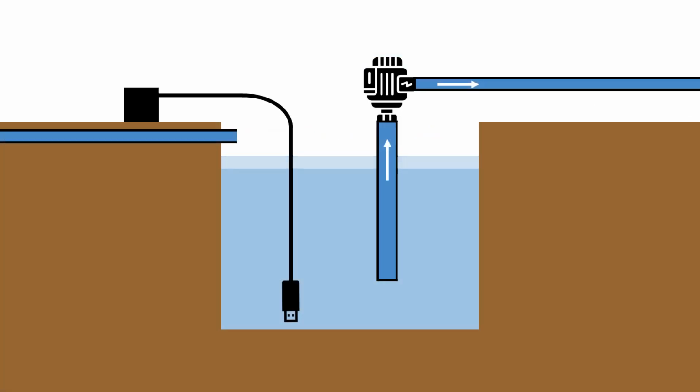Here's what happens with the programming. When the cistern drains down to that lowest level and the sensor reads 0.86 PSI or less, Program 10 will start filling it. The program can run as long as 4 hours, but when the pressure sensor reads 4.3 PSI or more, the program will stop before the cistern overfills.